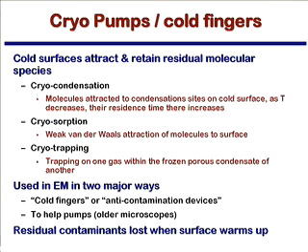Now, the thing about this is if the cryo cold finger warms up, then those extra molecules that you trapped that way will go away. And so if you're working on the microscope and using the cold finger, you have to keep it cold by supplying liquid nitrogen, usually every couple of hours or so. And then at the end of the day, you take your sample out and do a specific sequence where you warm that thing up to get rid of all the stuff that was stuck there while you were operating the microscope.